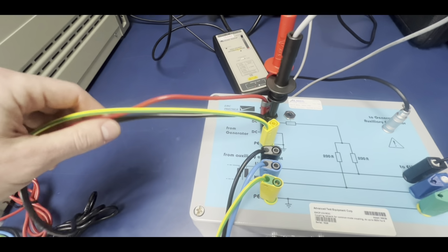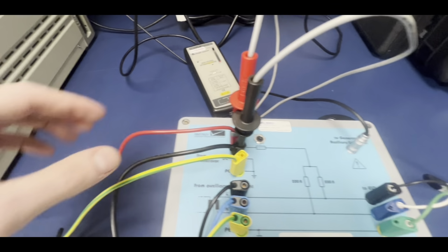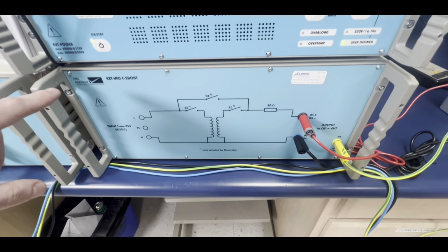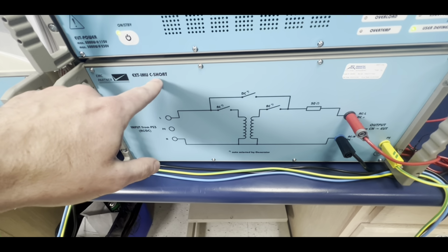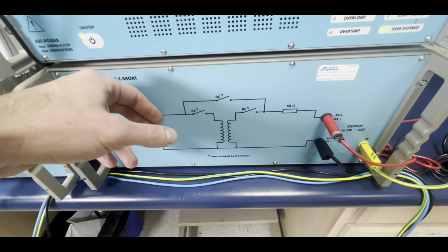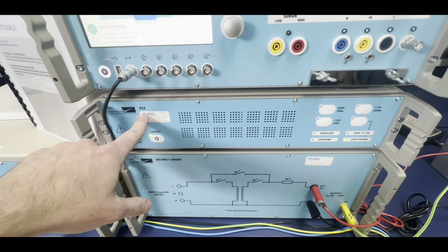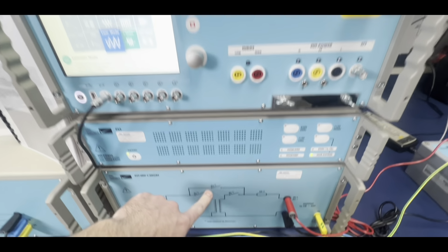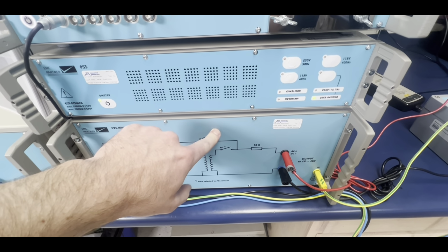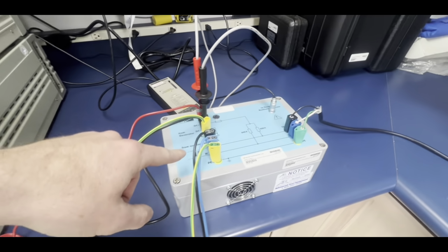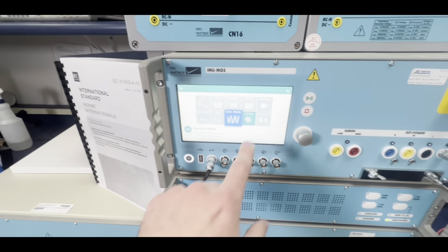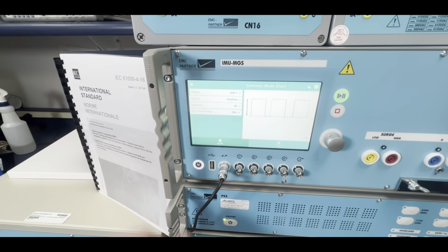The signal then that comes from the generator goes in right here, and we also have a differential probe so we can monitor our waveforms on the oscilloscope. That is currently coming through the C-short extension, which is essentially an amplifier that gets powered by the PS3, and this takes the signal from the generator, amplifies it to the 300 volt level, and then injects it onto the device through this guy. So let's go take a look at these settings here.